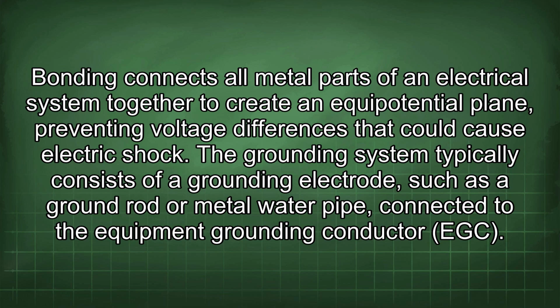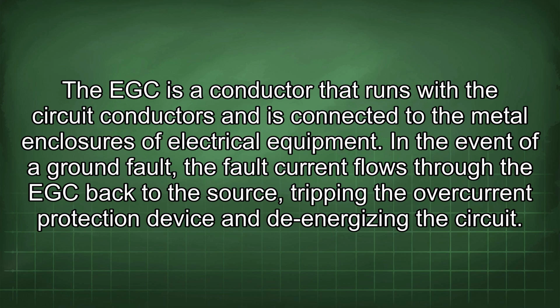The grounding system typically consists of a grounding electrode, such as a ground rod or metal water pipe, connected to the equipment grounding conductor, or EGC. The EGC is a conductor that runs with the circuit conductors and is connected to the metal enclosures of electrical equipment. In the event of a ground fault, the fault current flows through the EGC back to the source, tripping the overcurrent protection device and de-energizing the circuit.